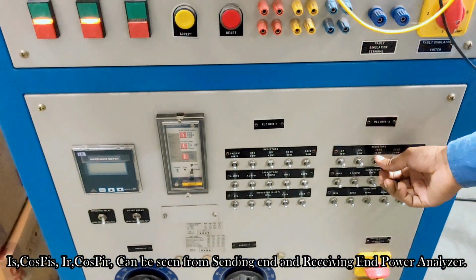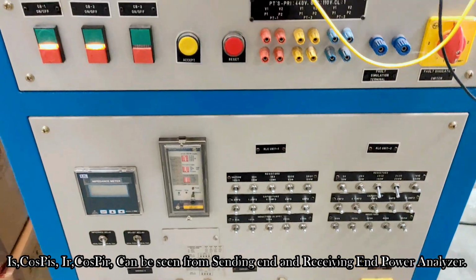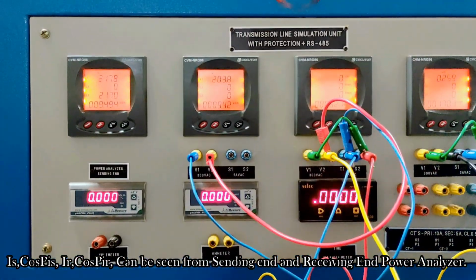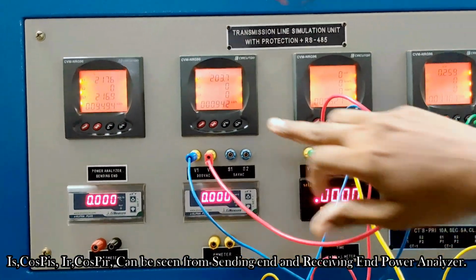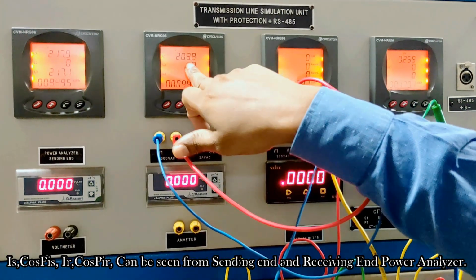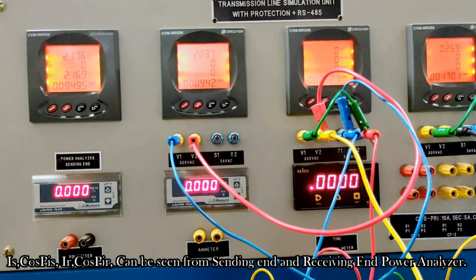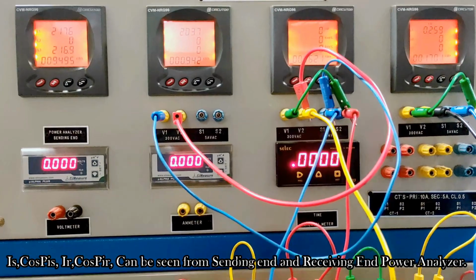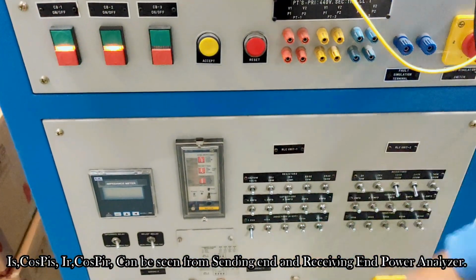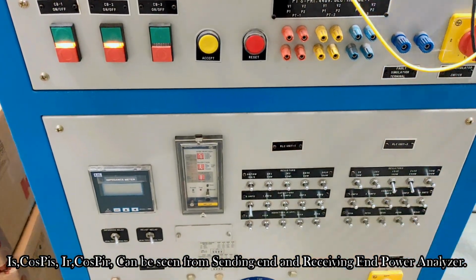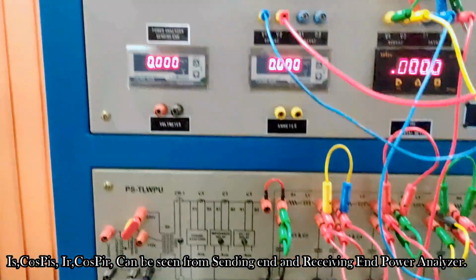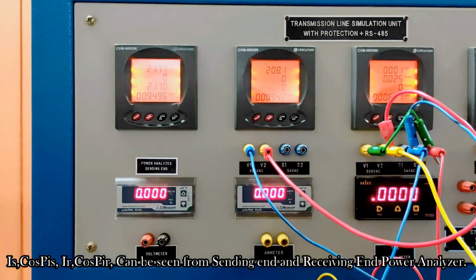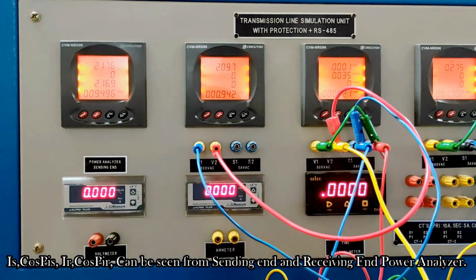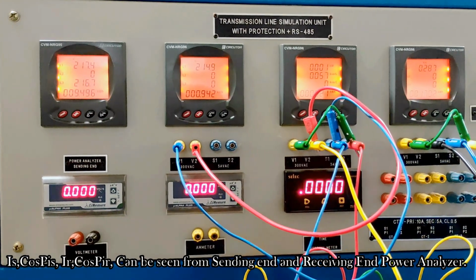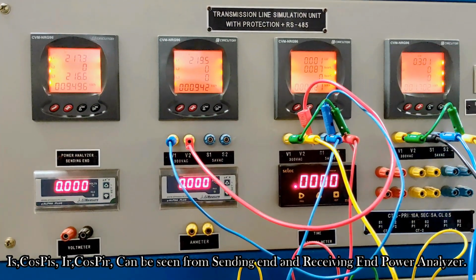So now I will turn on the 100 watt switch. Now power becomes 200 plus 100, 300 watt, and as you can see here, our voltage is again reduced to 203, and we need the capacitive reactive power to increase the voltage. So I will turn on the capacitor. The voltage is increased to 206. Once again the voltage is increased to 209, and then to 219.